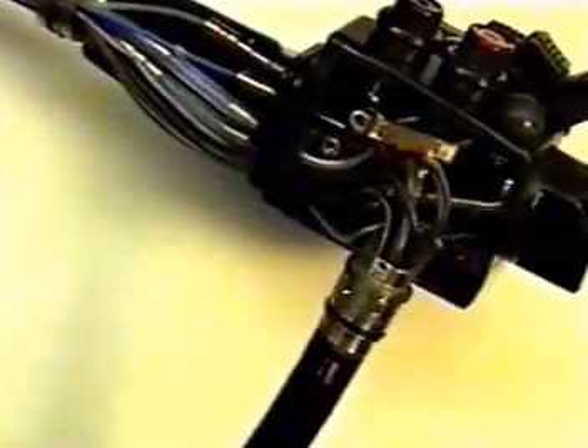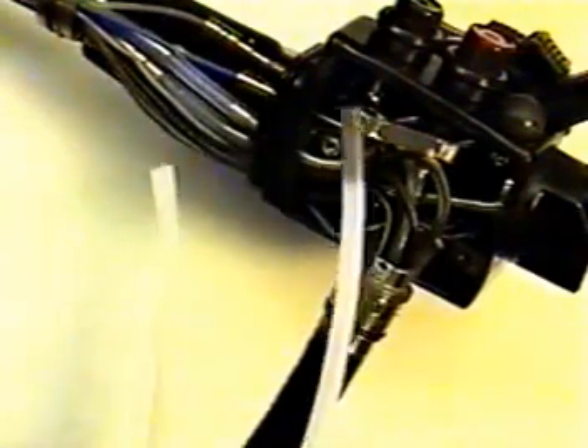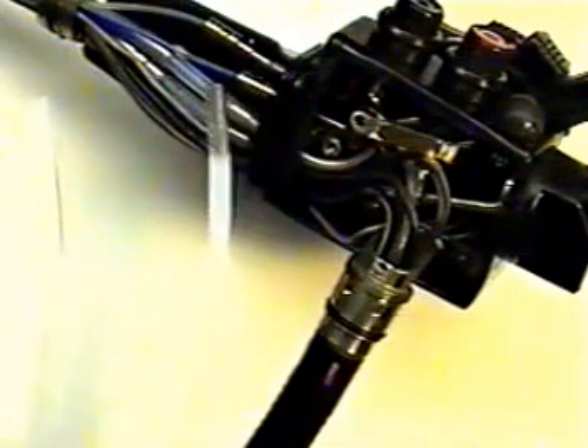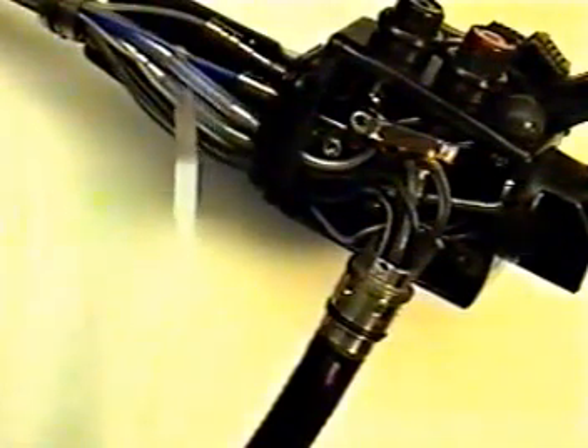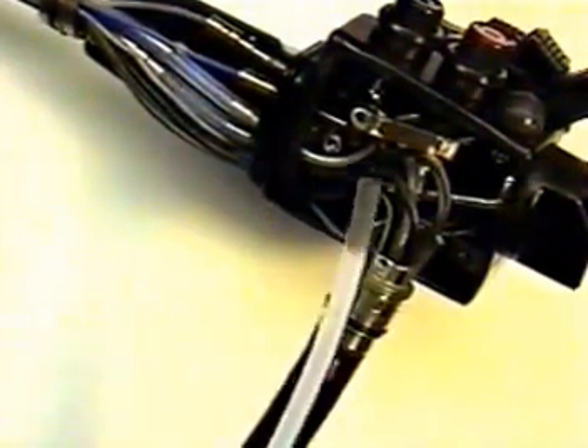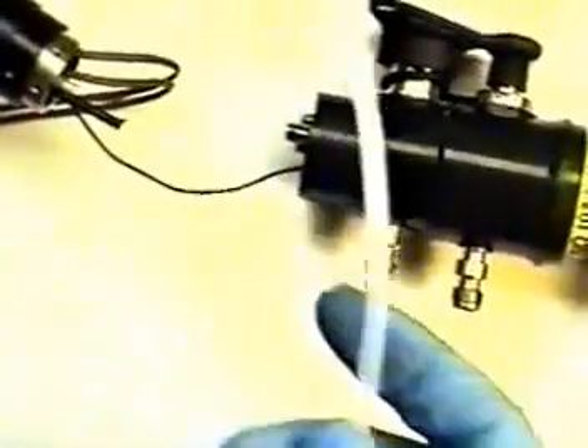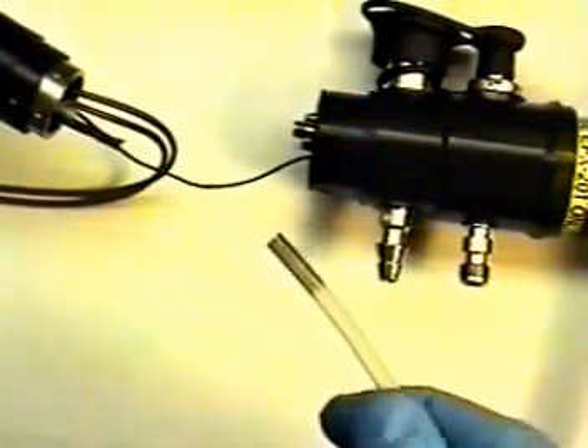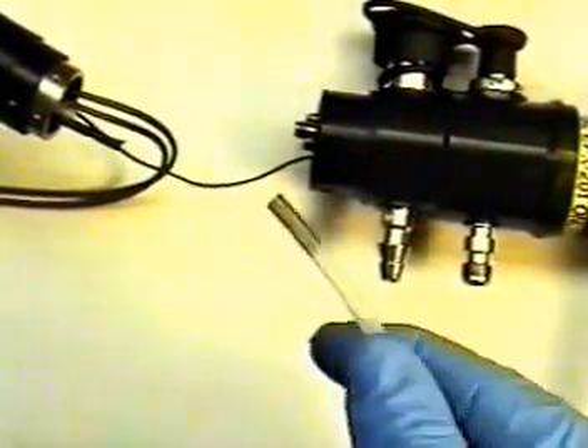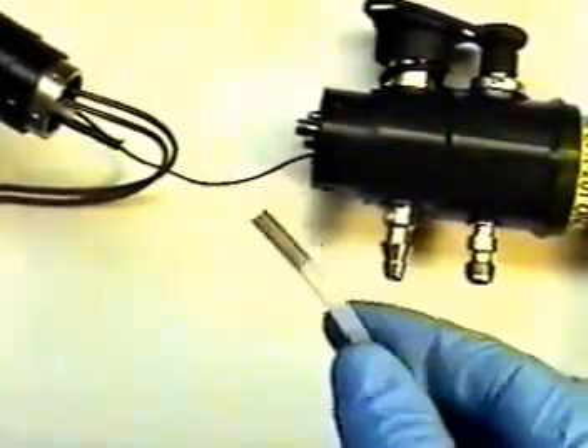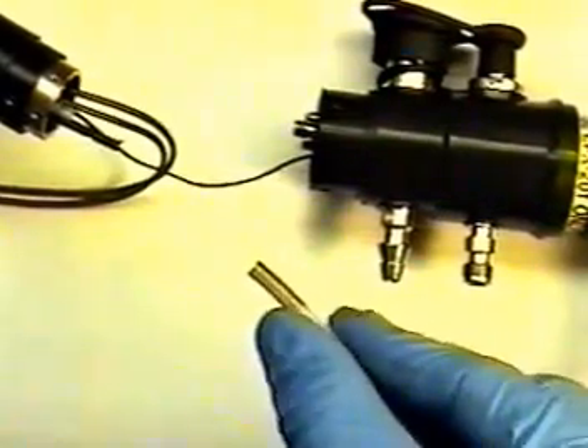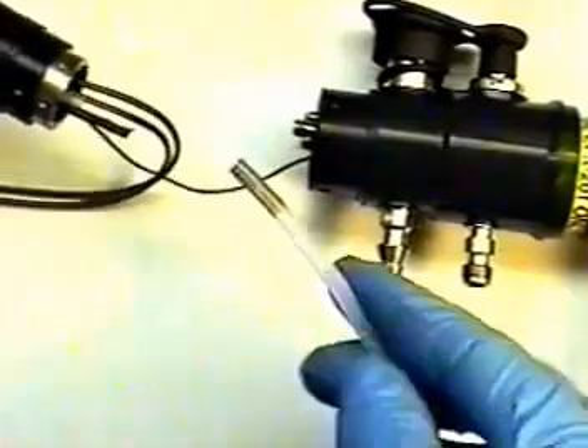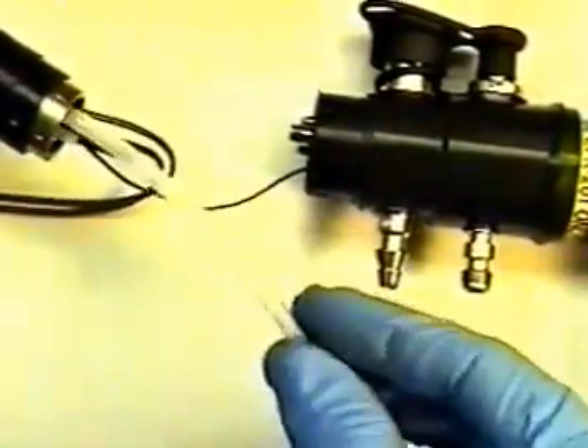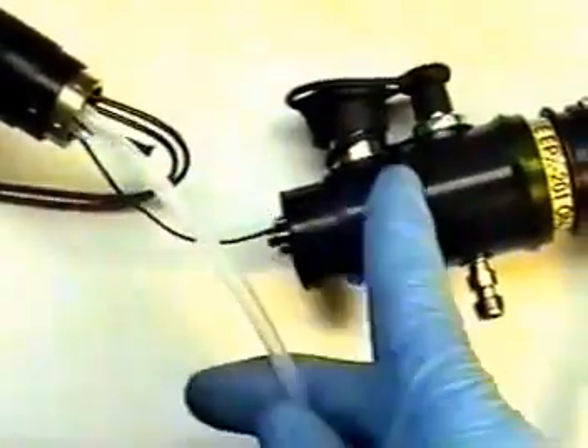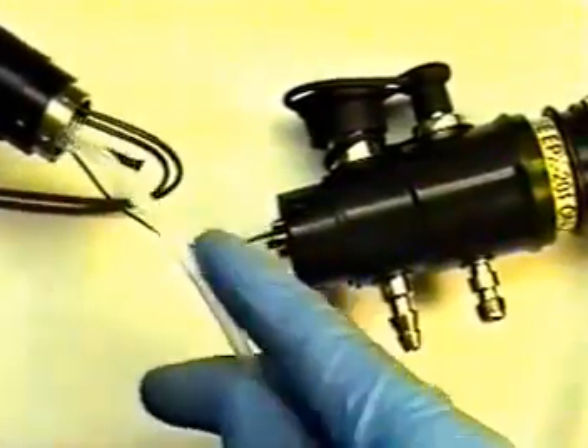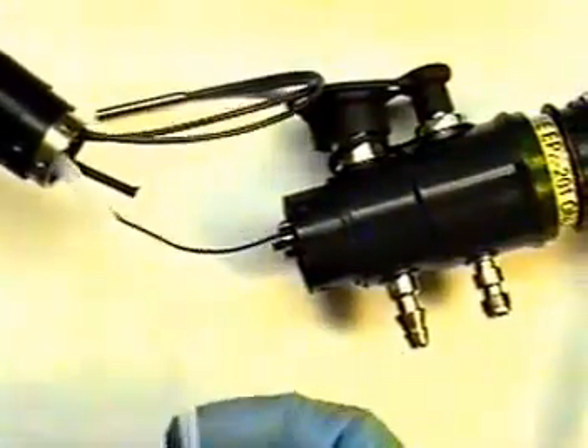Once Phillips screws have been tightened, we will now need to pass through our final channel, and that will be our suction channel. You can use a part number SP ST 3.7 suction channel to pass through umbilical section. Pass the suction tubing through the umbilical section, passing through the etched portion of the channel first. This portion will allow our glue to adhere properly to this Teflon tubing. Pass the tube through the umbilical section, to which our connector for air, water, suction, and light guide is attached.